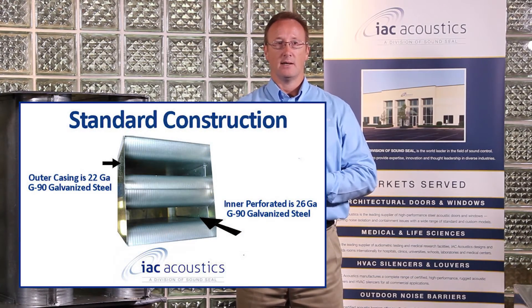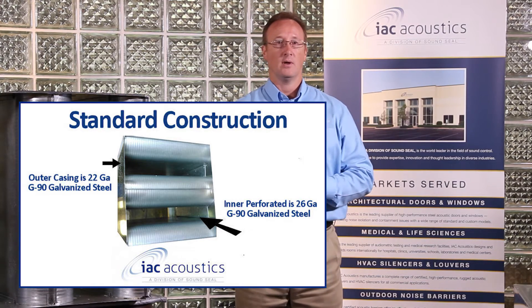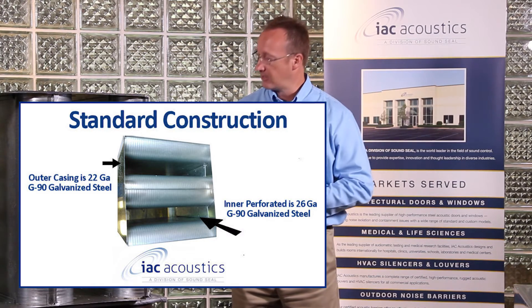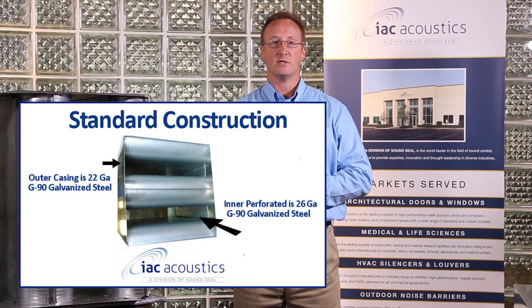Standard construction for our commercial series silencer is G90 galvanized material, a 22 gauge outer casing, and a 26 gauge perforated interior. We can also provide different types of material gauges should an engineer specify this, and these silencers also can come in 304 or 316 stainless steel.